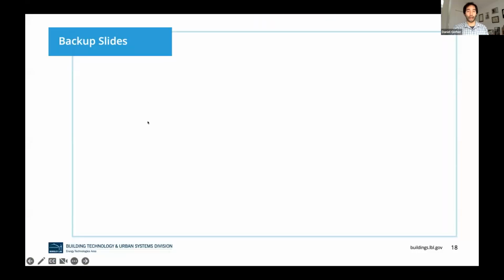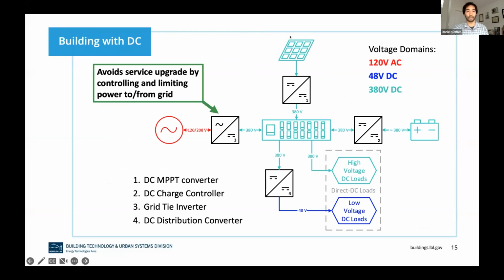Ted asks, is the 120 volt/208 volt to DC 380 volt converter efficient, low losses? I think you're asking about this grid tie inverter. From the data points I've collected, this type of conversion, when you have a bidirectional converter, is maybe around 93-94% efficient.